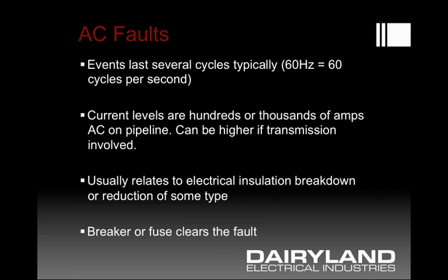An AC fault is something that will typically last several cycles. The level it reaches could be hundreds or thousands of amps, or even tens of thousands of amps. What the pipeline actually sees is generally less than that number — unless there was some direct bond between a transmission line grounding system and a pipeline, in which case values could be much higher. A direct bond would represent the worst case condition. An electrical fault occurs when there's some kind of insulation breakdown, an arc occurs, and current flows for the time duration until a breaker clears the fault. Usually that's several cycles of a 60 Hz or 50 Hz waveform — a relatively fast event, but still much longer than a lightning event.